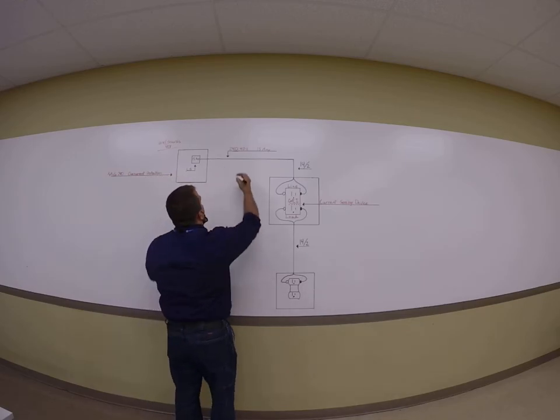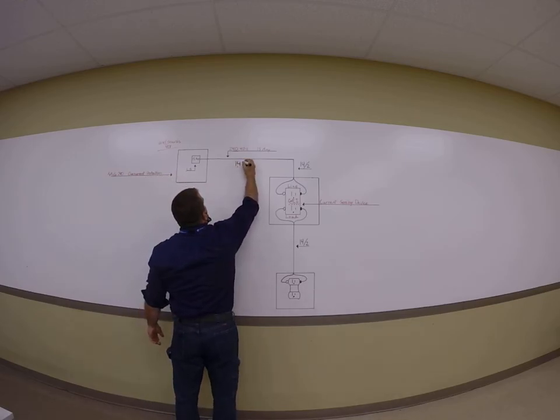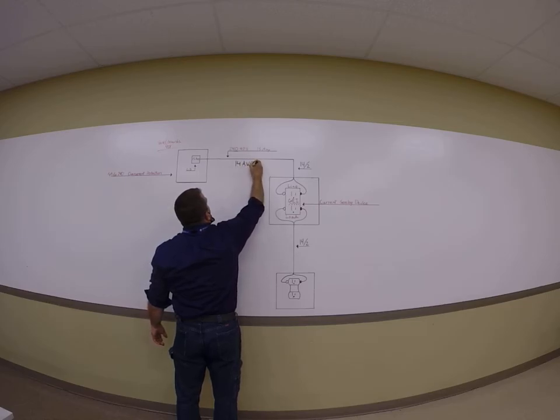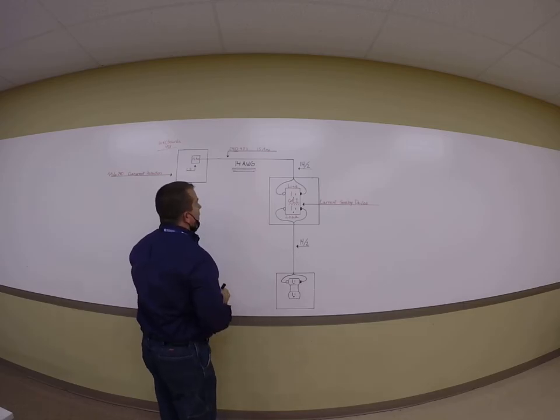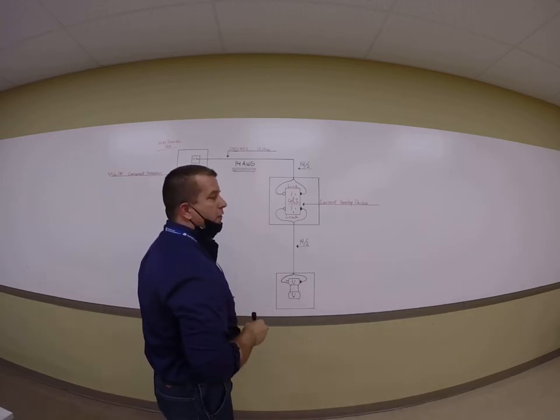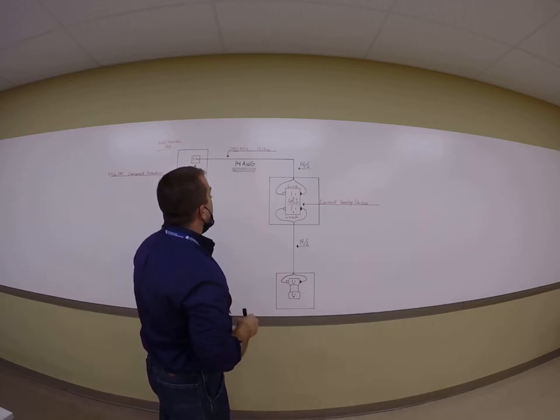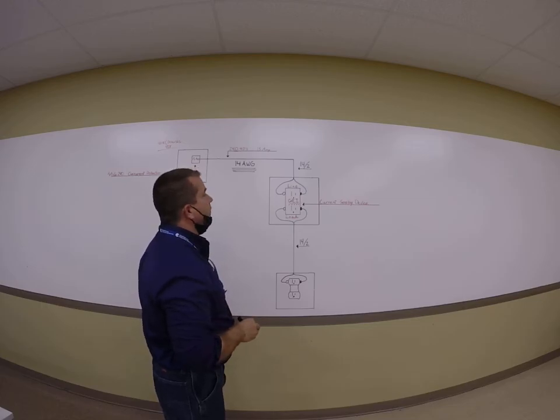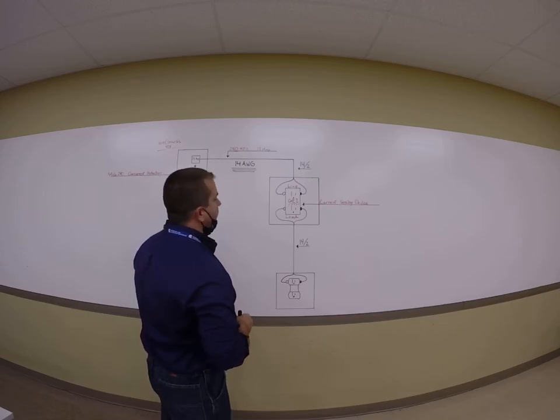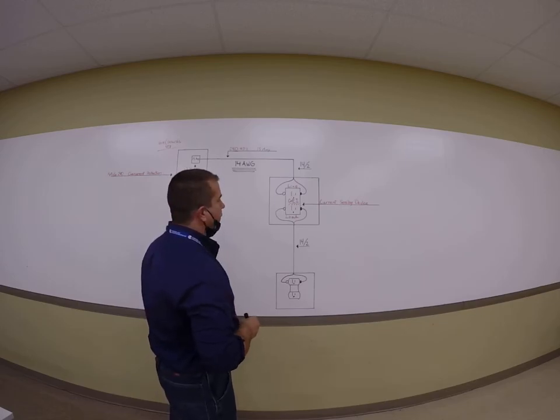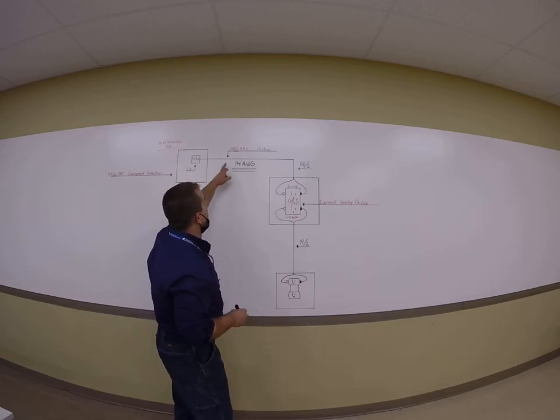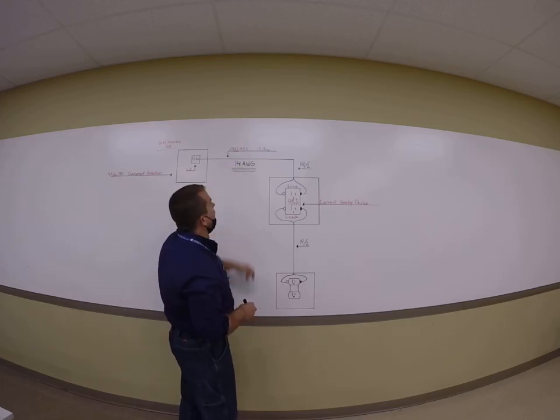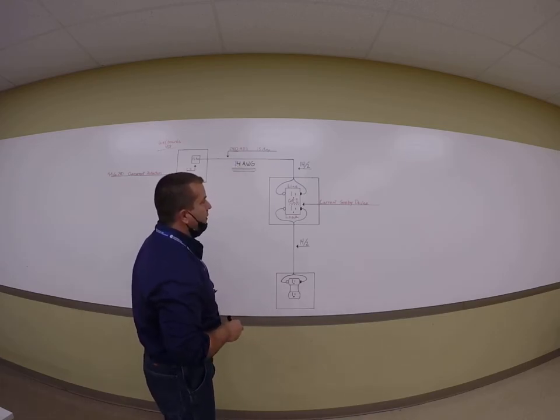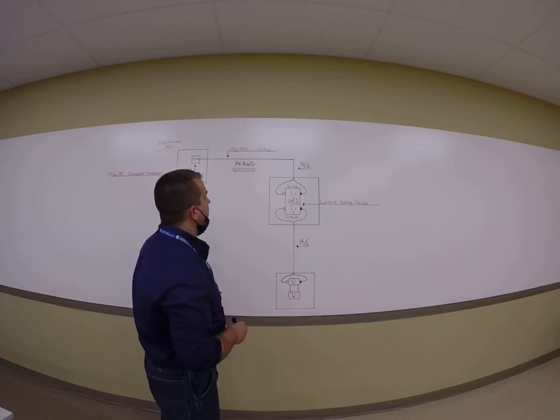14 gauge wire. Unless it meets the exceptions in mostly Article 430 and 440, 14 gauge wire has to be tied onto a 15 amp breaker. Most of the exceptions, as I said, are in 440 or 430. The article that says small conductors for this is 240.4(D)(3), 14 gauge wire and a 15 amp breaker.